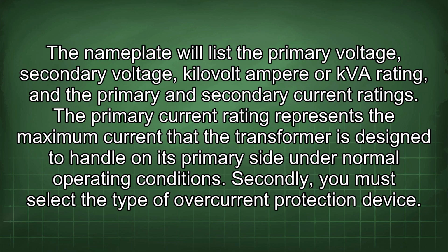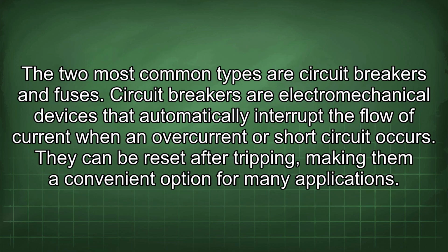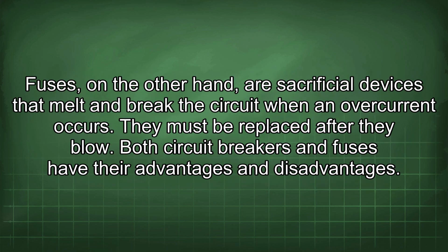Secondly, you must select the type of overcurrent protection device. The two most common types are circuit breakers and fuses. Circuit breakers are electromechanical devices that automatically interrupt the flow of current when an overcurrent or short circuit occurs. They can be reset after tripping, making them a convenient option for many applications. Fuses, on the other hand, are sacrificial devices that melt and break the circuit when an overcurrent occurs. They must be replaced after they blow.